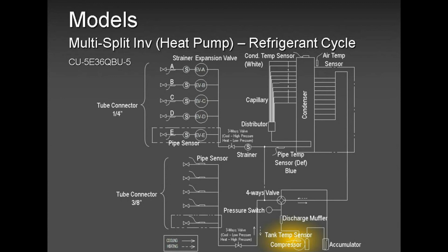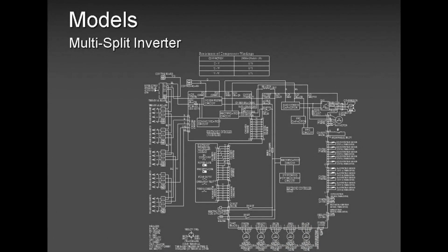So, what is this slide showing? It shows you 5 indoor units. 1, 2, 3, 4, 5. I know it's not very clear to you. It's not very clear to me. But basically, it just shows you the refrigerant circuit. And this page, you can also find in our service manual, password free. That's your compressor. Hot gas, high temperature vapor is being discharged, goes here into our condenser in cool mode. High pressure liquid is out, goes into your indoor unit. Low pressure vapor comes back, and that's how it cycles. Back and forth, back and forth, back and forth. In heat mode, it's the opposite. Your evaporator becomes your condenser, and your condenser becomes your evaporator.